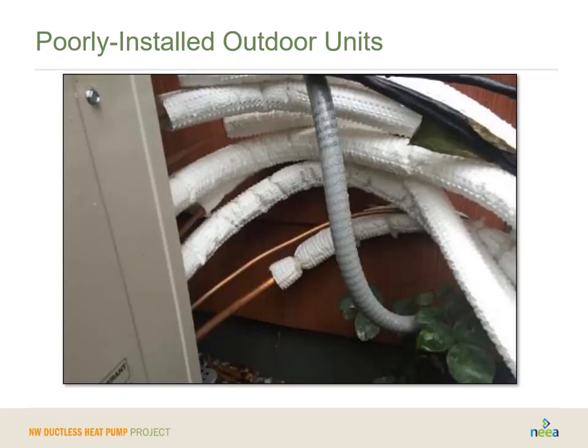You can probably guess what's going wrong here. We see refrigerant lines. Now, it has the good insulation on it that has UV protection, but it's not covering all of the line set. If it doesn't cover that line set, you could either get condensation on it, and you're certainly going to get reduced performance. This needs to be insulated so that if you're taking heat from outdoors and moving it inside or moving cool inside, you want to make sure it's actually going to get the job done and not lose a lot of that heat along its journey. And we do that by making sure they're properly insulated.